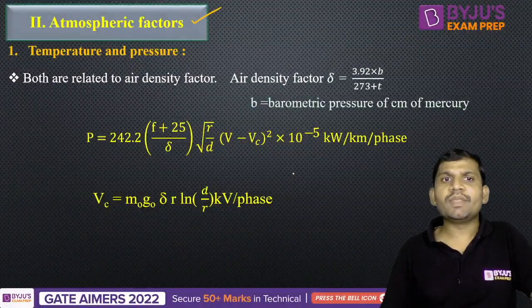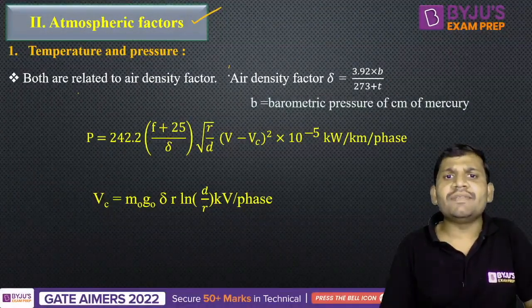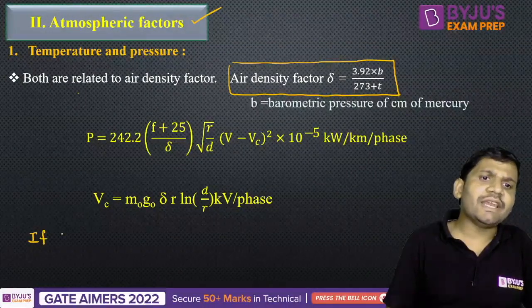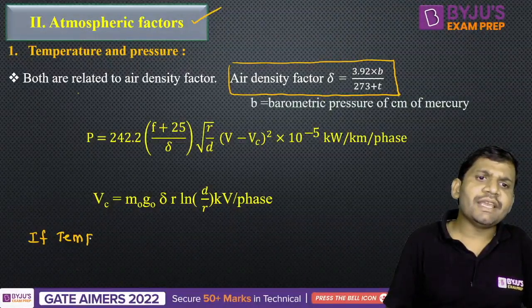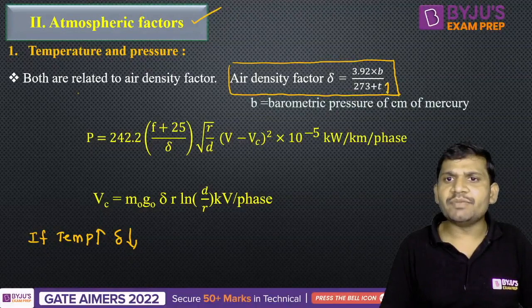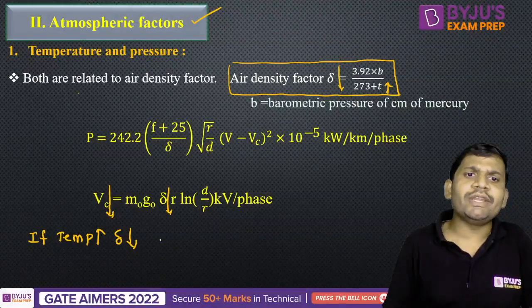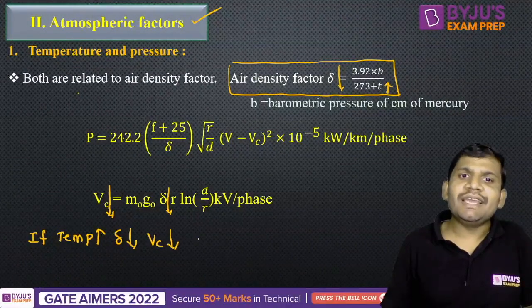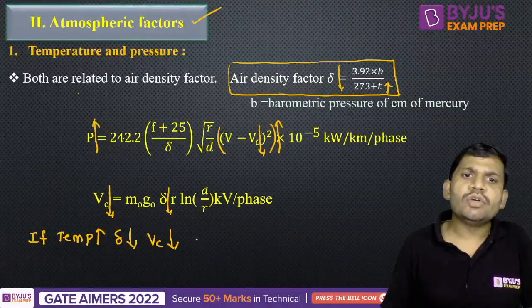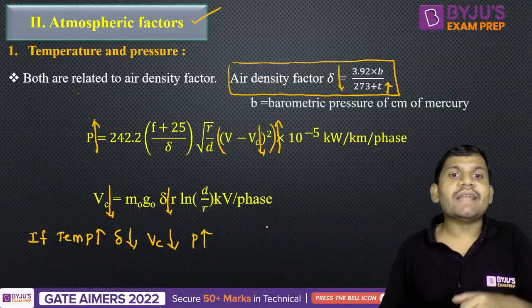Next, atmospheric factors. One factor is temperature and pressure, which depends on the air density factor. If temperature increases, the air density factor reduces. If the air density factor reduces, then the critical disruptive voltage reduces. When the critical disruptive voltage reduces, V minus Vc becomes more dominant and increases, so the power loss also increases. If the temperature is more, then the corona loss is also more.